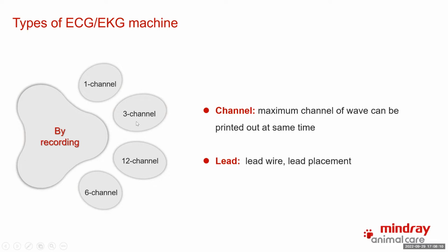From the bottom to the top of the thermal paper, there will be 12 waveforms in total. But the 3-channel ECG machine also uses the 12-lead placement. It will have 12 waveforms, but it cannot print out all 12 at the same time. So the 12 waveforms will be divided into 4 groups. It prints out the first 3, like lead 1, lead 2, lead 3, and then moves on to other leads like AVR, AVL, AVF, on a narrow thermal paper. So that's what 3-channel means. Right now in the market, 3-channel and 12-channel are the most popular ECG machine types.